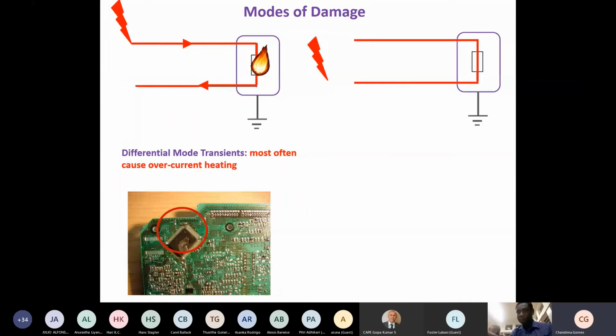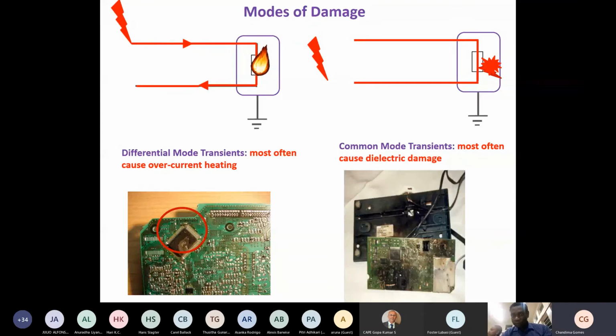And also if there is a nearby lightning, most often, as the power lines and the neutral wire are quite close to each other compared to the distance from those lines to the lightning strike, you get almost the same voltage induced in the line and neutral, so that there will be a potential difference between your line or neutral and the earth, so that you may get arcing from your line to the earth, which most often causes dielectric damage. And in these cases, you may see burn marks, which you usually don't see in the case of differential mode transients.